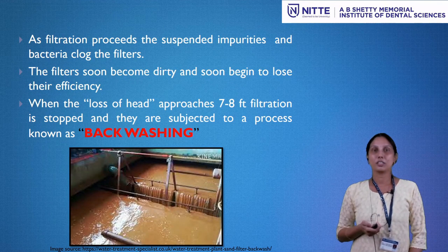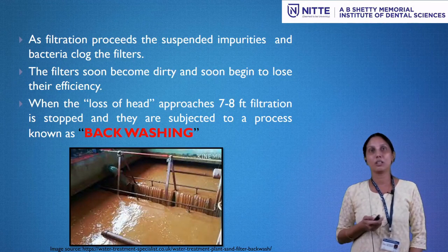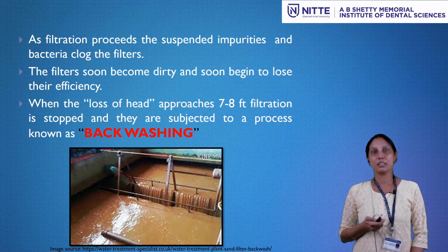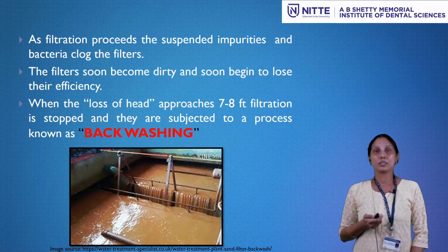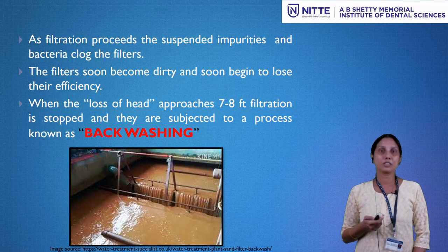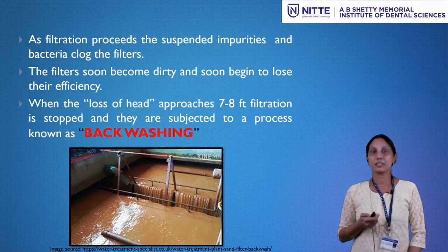As the filtration proceeds, the suspended impurities and the bacteria clog the filter bed. The filters soon become dirty and they begin to lose their efficiency. This is called loss of head. Now, when this loss of head reaches around 7 to 8 feet, the filtration process is stopped.